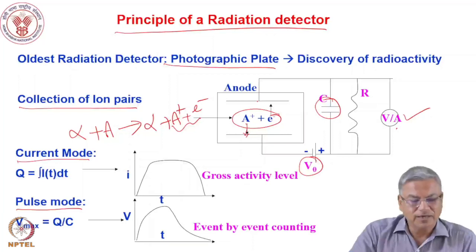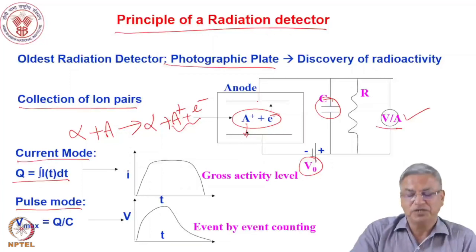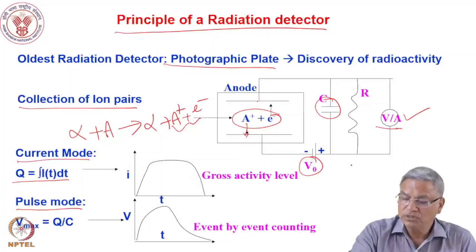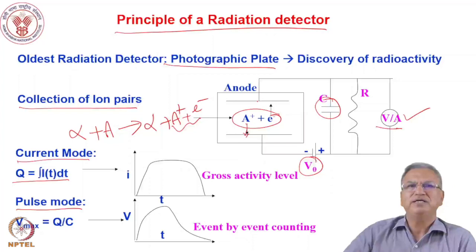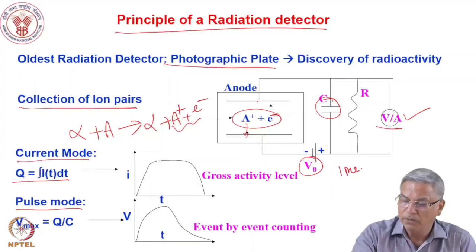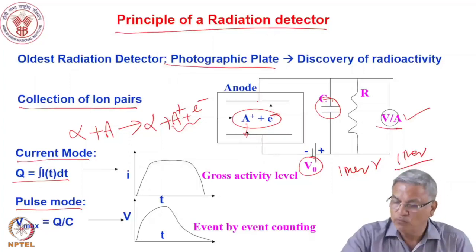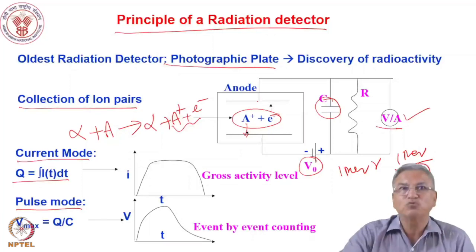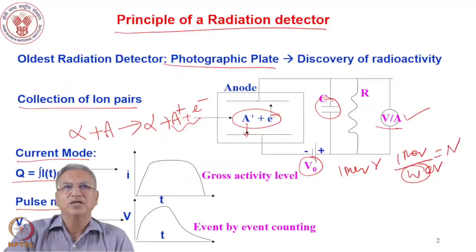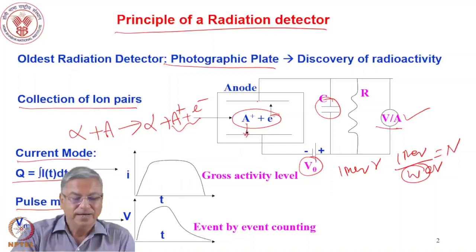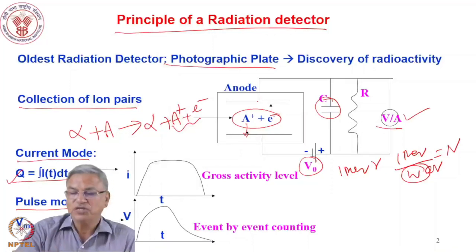When you measure the current in the circuit, whatever charge was created by the interaction of radiation with matter is the total charge. Suppose you have 1 MeV gamma rays coming in — it will produce ion pairs equal to E divided by W, where W is the energy required to produce one ion pair. These ion pairs are collected, so you are essentially collecting the charge. When this charge discharges through the ammeter, you see the current flowing in the circuit — it will be rising, become flat, and come down.